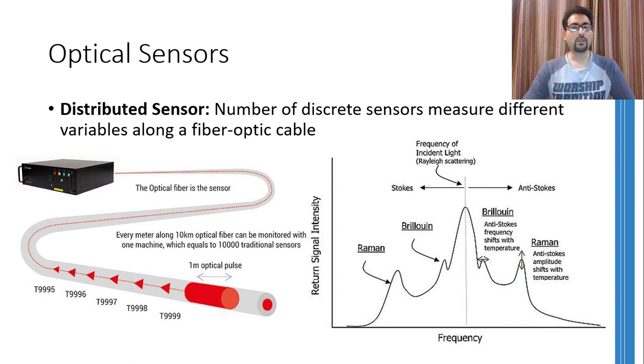Therefore, figuring out the frequency at which the Brillouin peak occurs and the amplitude of the Raman peak can tell us the temperature of the point from where the reflection occurred. As the light moves at lightning speed, it depends on the processing speed of the frequency analyzer how many reflections can be processed. The reflections that are being received are continuous because they are being generated at each and every point as the light wave is moving through the fiber optic cable.